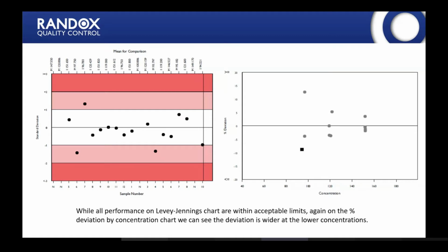And this means, so Stephen had showed how an instrument that has a bias would appear on the histogram. So if your instrument has a bias and there's less than 5 in your group, you'll end up being compared to the method mean, and you may find that for the samples where you run the method that you have a bias appearing here. So that will be reflected again on this chart depending on your level of comparison.